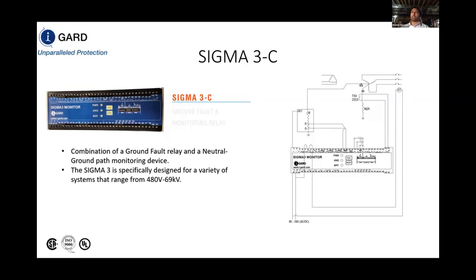This is our Sigma 3-C. It's an NGR monitoring relay and ground fault relay. It's able to detect abnormalities on the neutral grounding resistor, as well as monitor for ground faults flowing through the neutral. It has an operating range between 480 volts to 69 kV.